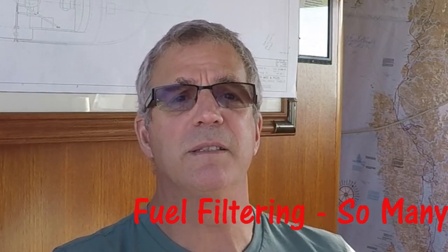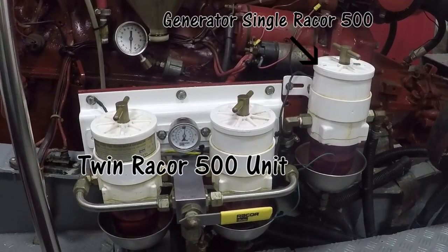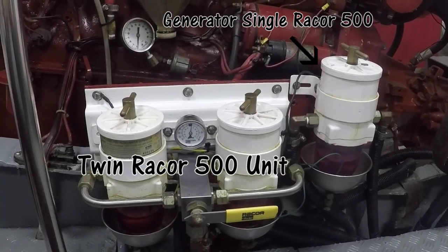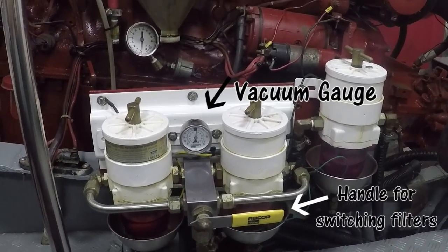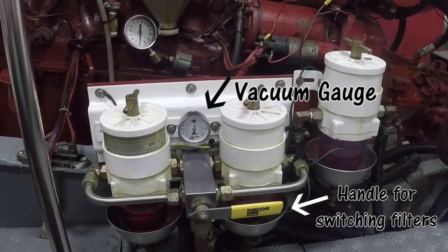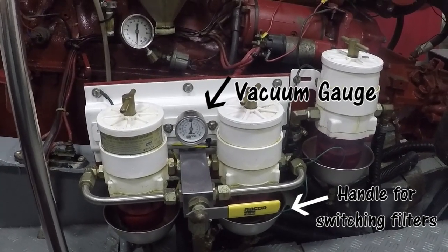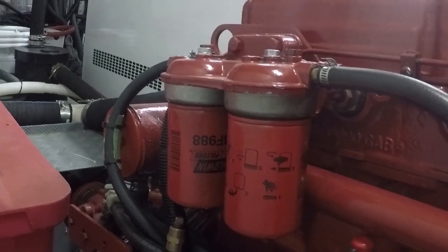Fuel filtering — so many filters. On SeaVenture, the fuel comes from the tank of our choice, controlled with a series of valves, then goes to the Racor filters. We have twin Racor 500s, which allow you to choose which filter the fuel is going through and to switch filters on the fly with the yellow handle. They're also equipped with a vacuum gauge, which records the vacuum required to pull fuel through the filter. As the filter gets clogged, the required vacuum increases. After the Racor filter, it goes through two additional filters on the starboard side of the engines before the injector pump. The end result is very clean fuel getting to the engines.